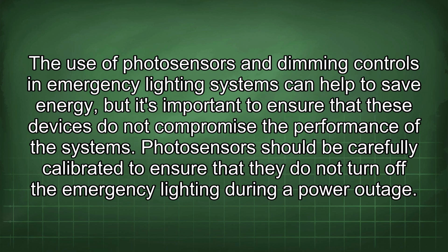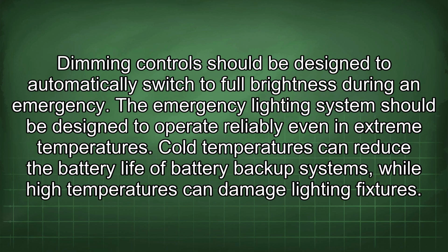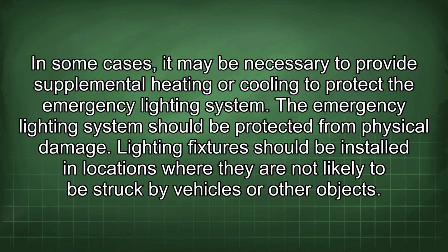Photosensors should be carefully calibrated to ensure that they do not turn off the emergency lighting during a power outage. Dimming controls should be designed to automatically switch to full brightness during an emergency. The emergency lighting system should be designed to operate reliably even in extreme temperatures. Cold temperatures can reduce the battery life of battery backup systems, while high temperatures can damage lighting fixtures. In some cases, it may be necessary to provide supplemental heating or cooling to protect the emergency lighting system.